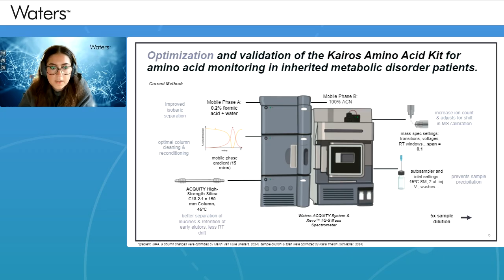And that's because we were seeing an issue called detector saturation in our high calibrators. So our peaks were looking like this. You can see it has a flat peak top when it should have looked something like that. And when we were originally processing the linearity, you can see this plateau at the high calibrator range. I've added in 2 additional calibrator points here just by diluting calibrator 7 to better visualize this.